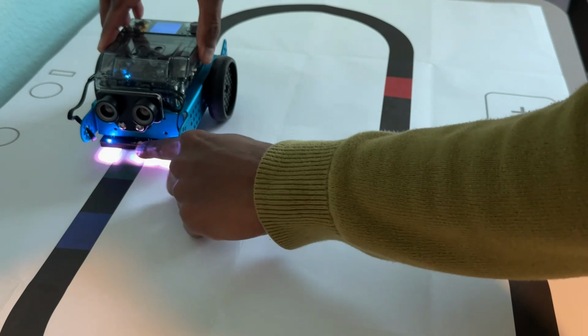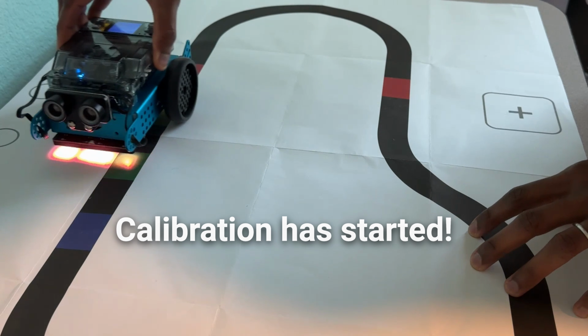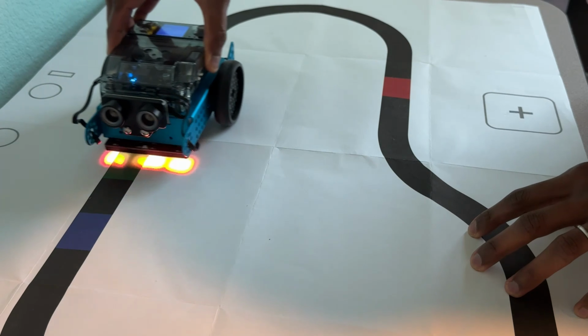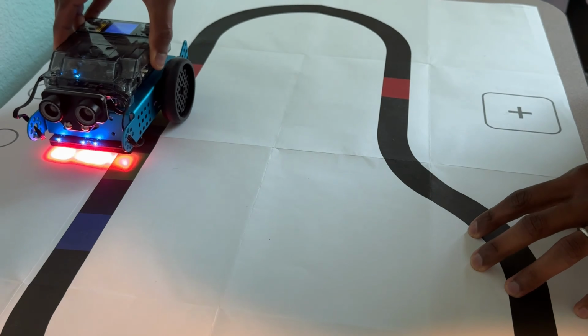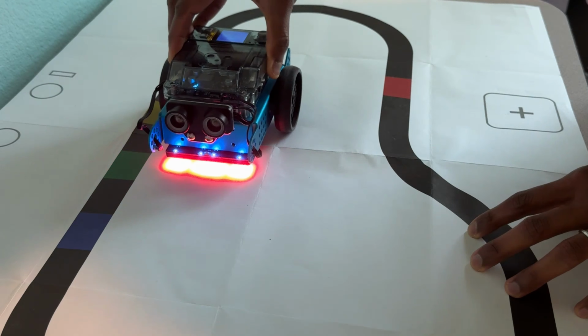The 4 blue indicator LEDs and the fill lights start flashing. At this point, calibration has started. Sway or move the 4 sensors over and out of the black line until the flashing stops.